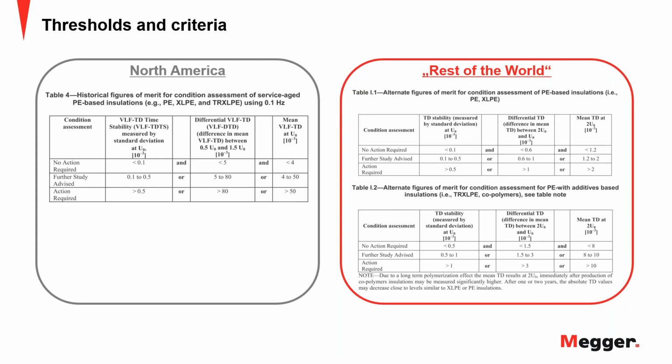Okay. I'm not sure, maybe Robert can comment on this. I'm not aware of any tan delta table in any of the European standards, whether there is one. There didn't used to be one. Maybe there is one now, I don't know. But maybe Robert can comment on that. No, there's just, you know, common test practices which are partially sketched in the IEEE 400 guide.